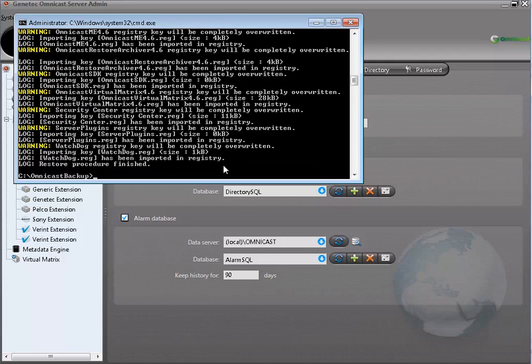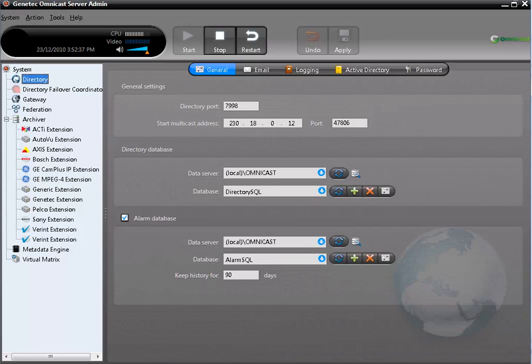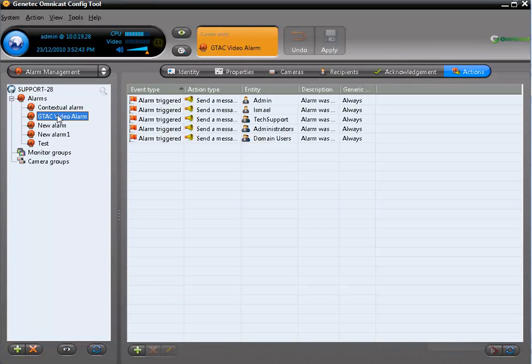The restore is now complete. You can now restart the services you stopped — in this case, the directory service. My database properties show 153 entities, which was the number I had before deleting my alarm. If I go back to the config tool under alarm management, you can notice that the alarm I deleted before the restore is now back.